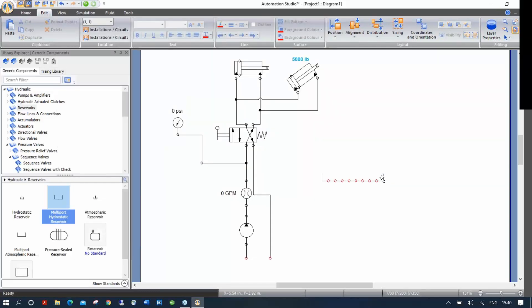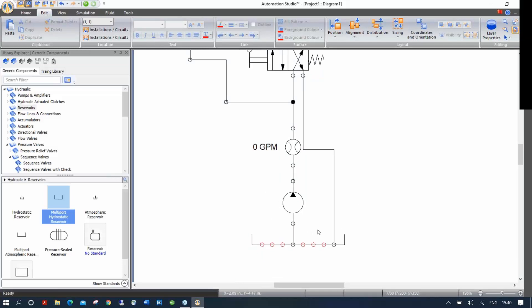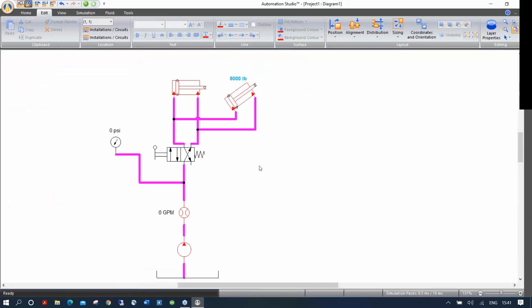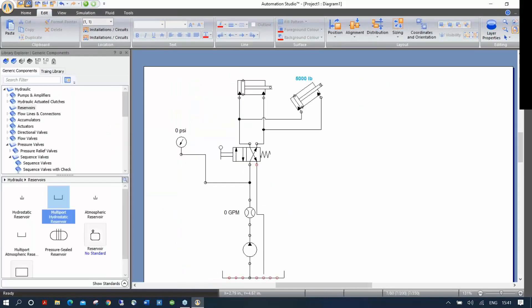You can drag the multi-port reservoir down and connect multiple lines to it. If you leave a port open in Automation Studio, once you launch the simulation the open ports will automatically be plugged. So if a port isn't connected and you simulate, it acts like there's a plug — no flow exits. For example, if I delete a return line and simulate, the oil has nowhere to go and pressure shoots up to 30,000 PSI. So always ensure your circuit is properly connected.